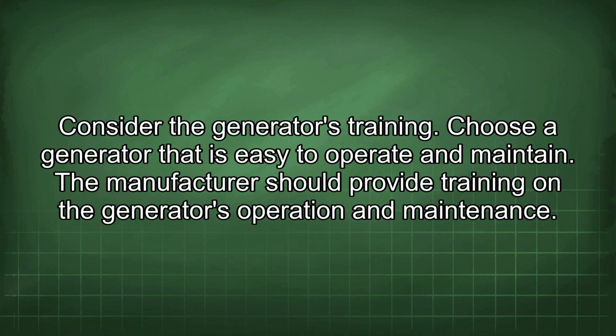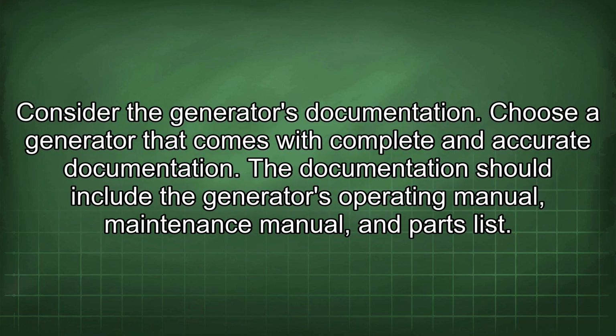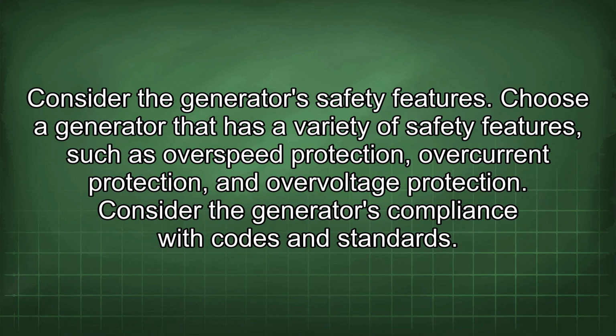Consider the generator's training. Choose a generator that is easy to operate and maintain. The manufacturer should provide training on the generator's operation and maintenance. Consider the generator's documentation. Choose a generator that comes with complete and accurate documentation. The documentation should include the generator's operating manual, maintenance manual, and parts list. Consider the generator's safety features. Choose a generator that has a variety of safety features, such as overspeed protection, overcurrent protection, and overvoltage protection.